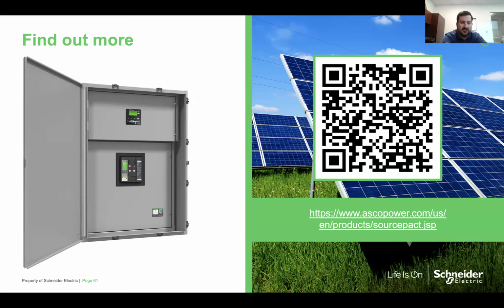Yeah, I did see that question come in and read through it. Again, let's follow up afterwards for a more detailed conversation. But the gist of it, if I'm reading this correctly, is a situation that's becoming commonplace: you have EVs on a dedicated utility, and a nearby building with a microgrid that is backed up. When power goes down on the EVs from their main utility, you want to switch them over to the building's microgrid, which could still be up since it has some resiliency sources. The short version is that yes, I don't see any reason why that wouldn't be possible.